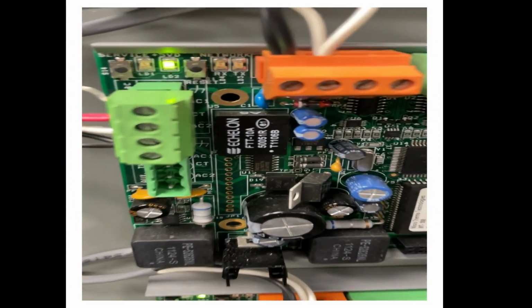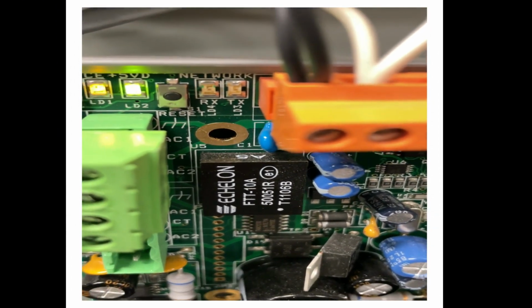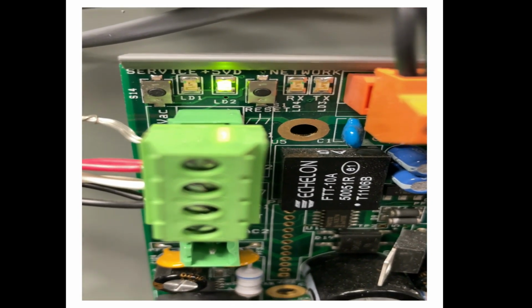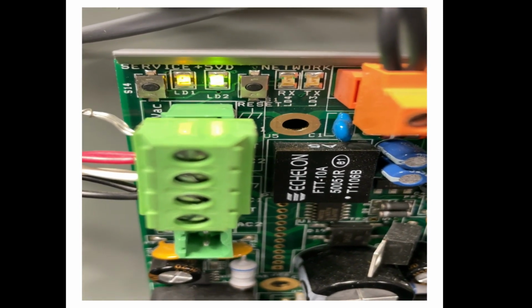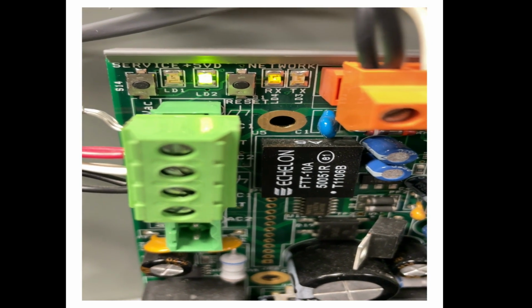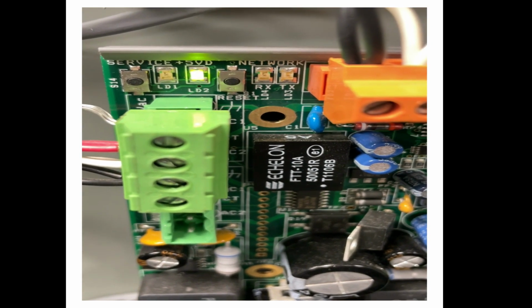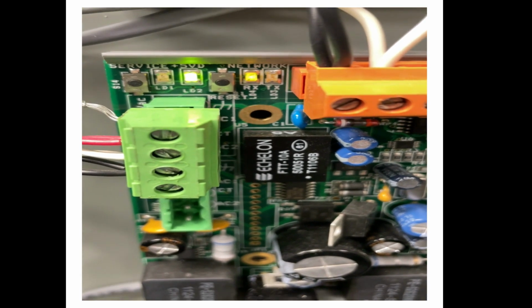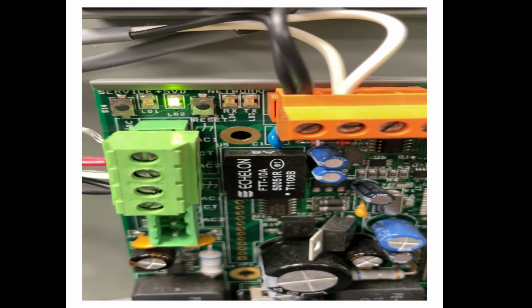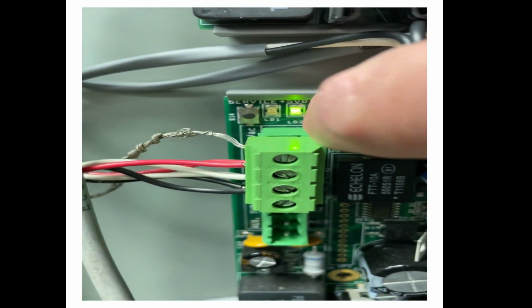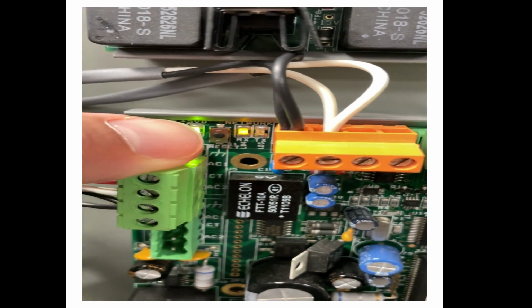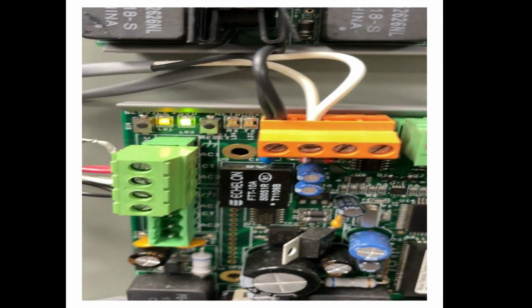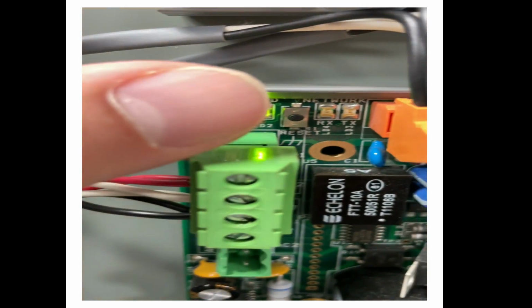The next thing you would like to check is the communication to and from the smart node. Now, we have a status light and we also have an RX and TX light, which indicates that the node is receiving and transmitting information on the network. So observe the lights. You should see activity on the RX and TX lights, and then on the status light for the MT500, you should see 1 second on, 4 seconds off, 1 second on, 4 seconds off.